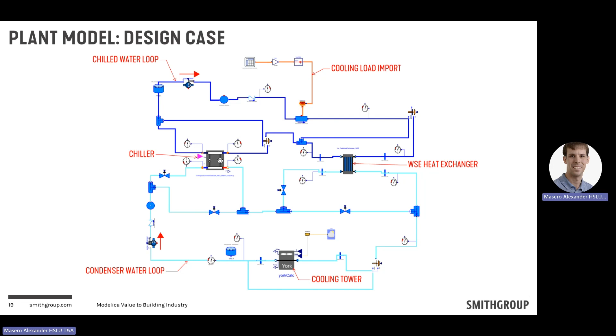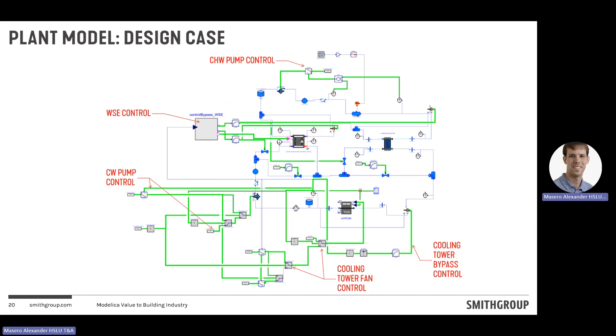This is some of the benefit we get from Modelica, as many in this room know — all the custom dynamic controls we use to make this more realistic, including bypass for freeze protection, cooling tower fan control, and condenser water pump control strategies, all being tested.